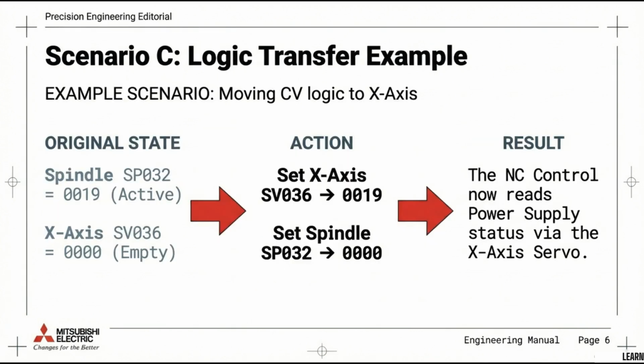For example, to move CV logic to the x-axis, set the active spindle value to the x-axis servo, and then set the spindle value to 0000. The NC control will now read power supply status via the x-axis servo.